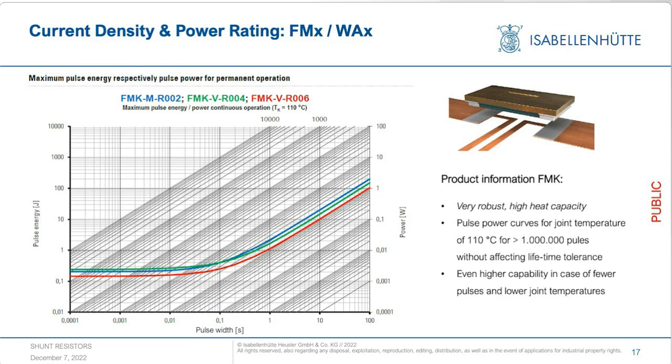I should mention that these curves are valid for joint temperatures of 110 degrees C. So if you have lower joint temperatures, the power rating can be even higher.